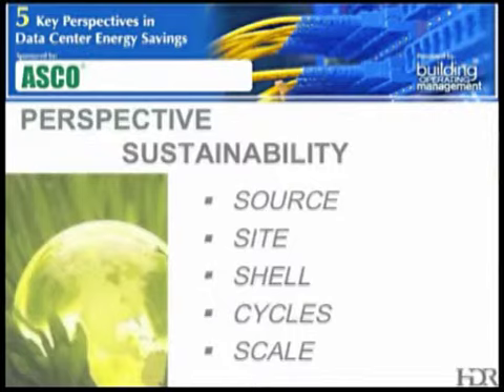Use that building mass for diurnal cooling. Look at high thermal mass as an option here, especially in conjunction with nighttime ventilation strategies. Those nighttime ventilation strategies can offer free cooling in a lot of climates. And in addition, a lot of utilities do offer off-peak electrical rates that can make overall savings for you. So if there's a way that you can do, say, nighttime cooling storage, it might be an effective way to reduce it from a cost standpoint.